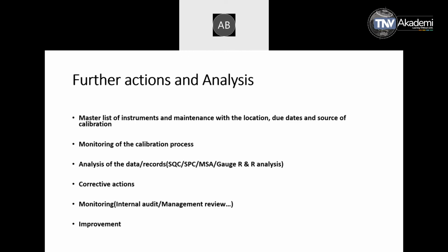They do not understand the concept of technical requirements, the errors, the measurement systems, and IS specification to control the whole calibration system. So I have always been making a point that internal audit of this calibration system should preferably be done by utilizing the technical team, the engineers who understand the requirements of instrument, who know how to use instrument, who know where to use instrument, where the instrument will be for indication purpose only, where it is at a stage where the final acceptance is coming and the item is going to be dispatched to the customer.